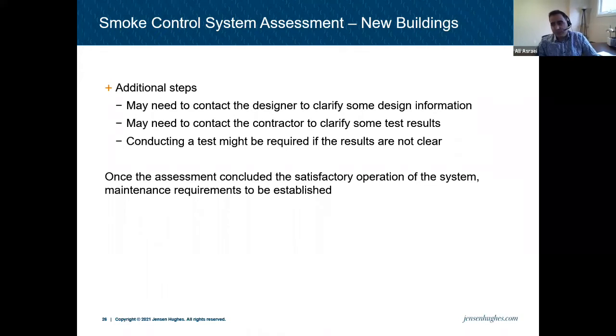There are additional steps in here, as I talked about. We may need to contact the designer to clarify some design information, or maybe the contractor to clarify some test results. And if you're not happy with the test results or not convinced that something was done properly, then at that point we make a decision to do a test ourselves to make sure we get the numbers and the numbers are right. So sometimes at the first step, you see the designer is not right. So you have to go back to the designer and bring it to their attention, which is not fun. The building is constructed, occupied and all that. So it's pretty hard. But anyway, if you're involved as an engineer, this is our job to do it.